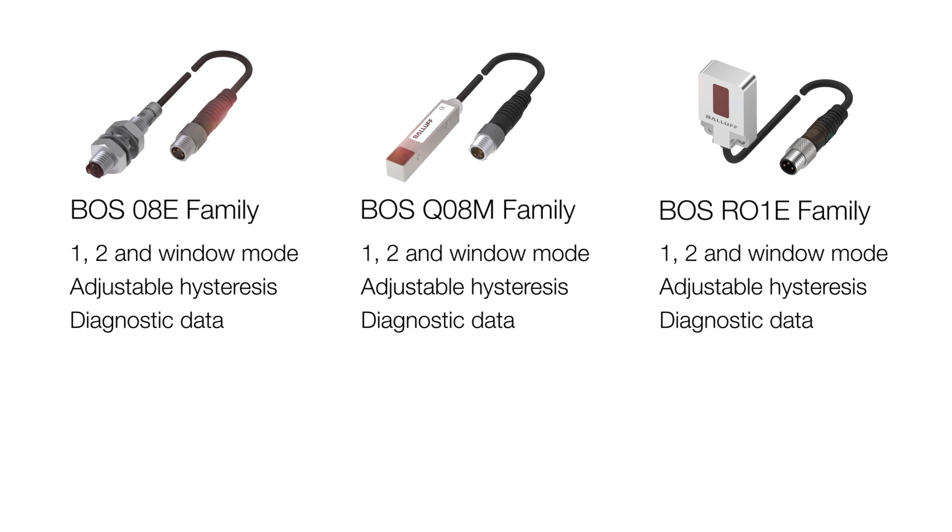The Q08M has the same IO-Link functionality as the 08E and the RO1E, plus you can get operating hours in two versions: one that is non-resettable, and one that you can reset for maintenance. In addition, you can configure delays — an on-delay, an off-delay, an on-off-delay, and also a one-shot.